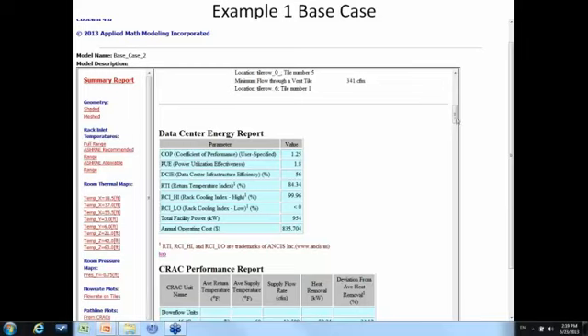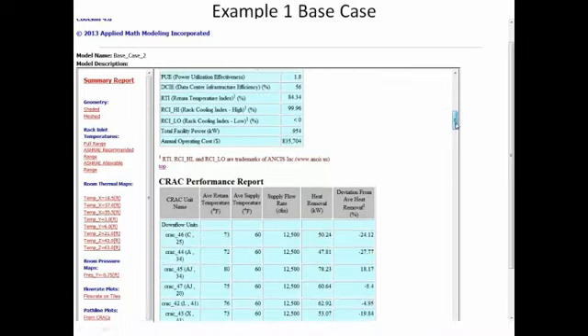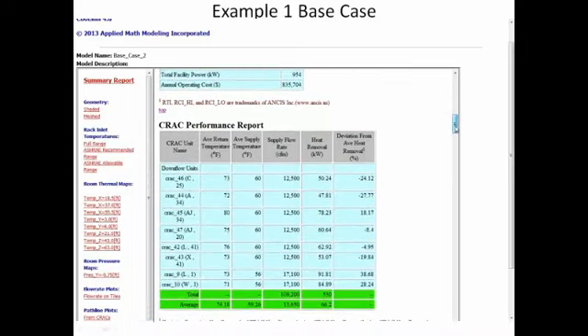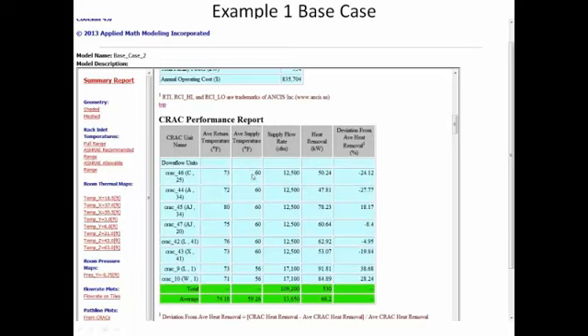That's correct. So let's go a little further down in our summary report here. And again, this is generated for every single run. We generate these reports. So here we are with CRAC performance, and these are the CRACs. You notice they're all running at 60 degrees of supply temp. So they're running very cold. The heat removed is shown here. There's quite a bit of variation in heat removed. Some units are pulling out a lot. These are the bigger units down here. These are the 30 kW units down here. But look at the variation even in the 20 kW units.